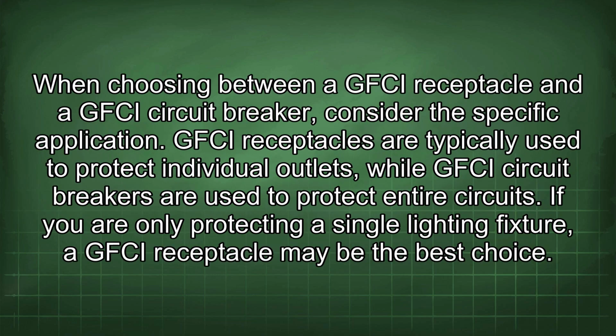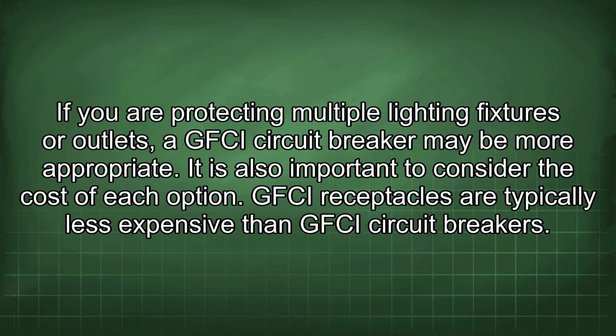When choosing between a GFCI receptacle and a GFCI circuit breaker, consider the specific application. GFCI receptacles are typically used to protect individual outlets, while GFCI circuit breakers are used to protect entire circuits. If you're only protecting a single lighting fixture, a GFCI receptacle may be the best choice. If you are protecting multiple lighting fixtures or outlets, the GFCI circuit breaker may be more appropriate.